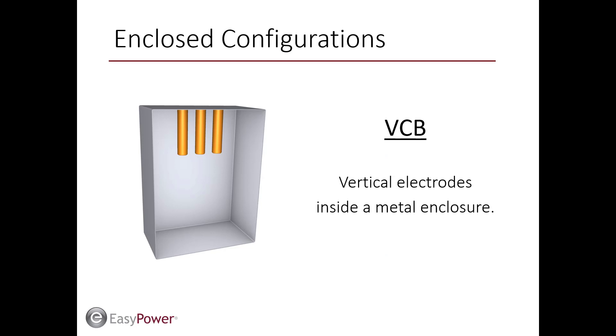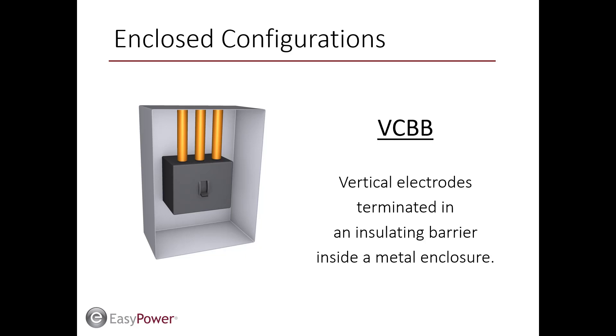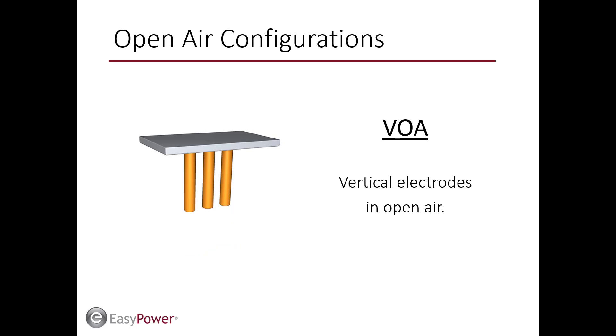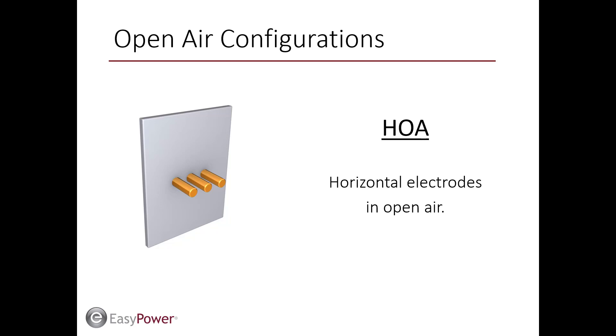The electrode configurations in the 2018 standard are: VCB — vertical electrodes inside a metal enclosure; VCBB — vertical electrodes terminating in an insulating barrier inside a metal enclosure; HCB — horizontal electrodes inside a metal enclosure; VOA — vertical electrodes in open air; HOA — horizontal electrodes in open air.